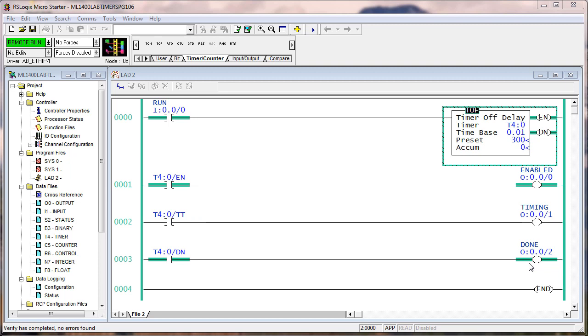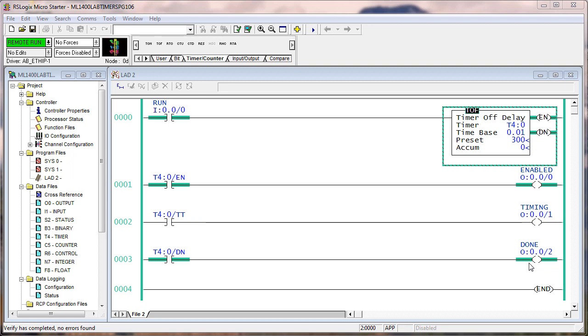So the question was, what could you say about the difference between a TON and a TOF instruction when addressing a timer data type in regards to resetting timer bits and the accumulate? When a TON is done, it is done, and the accumulate equals the preset. When a TOF is done, it is not done, and when it is done, for real, it's no longer done.